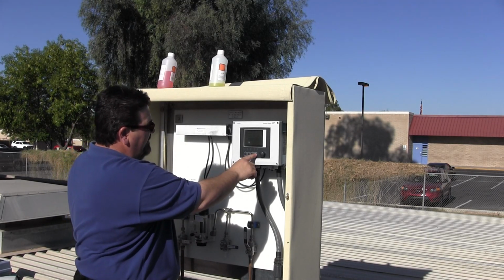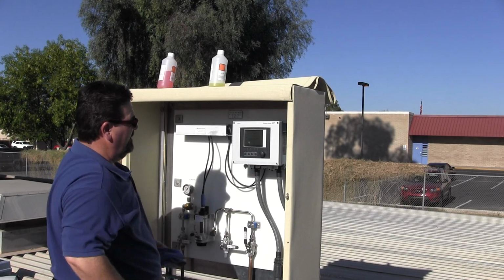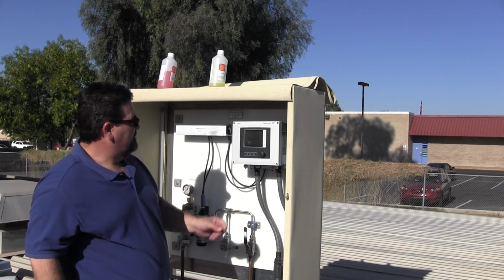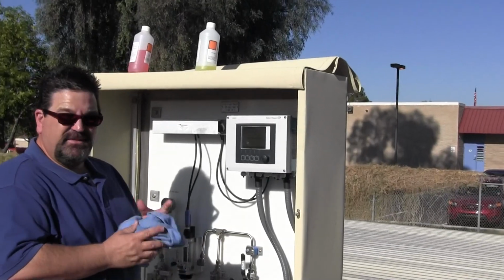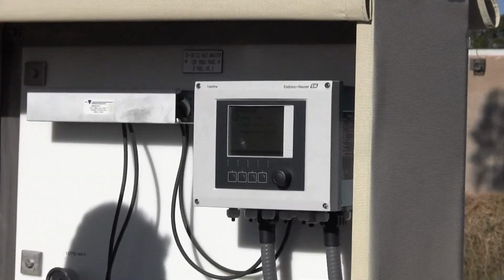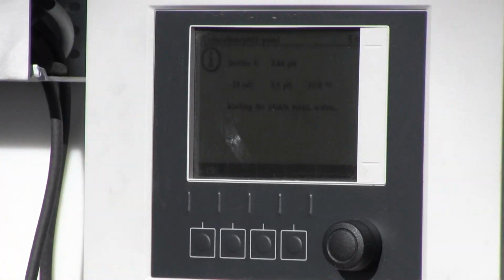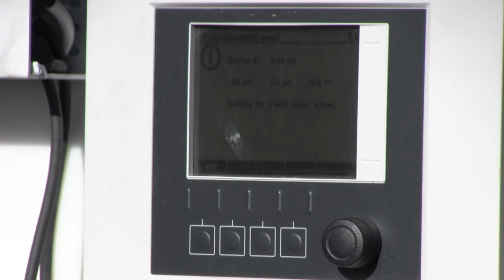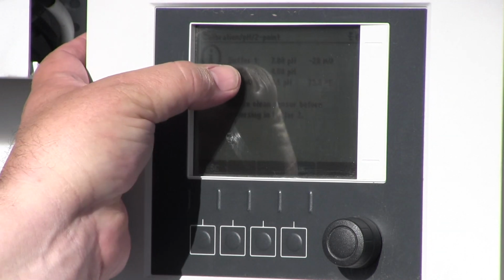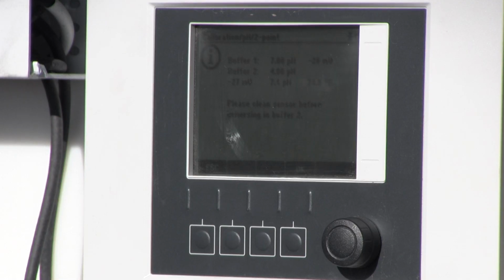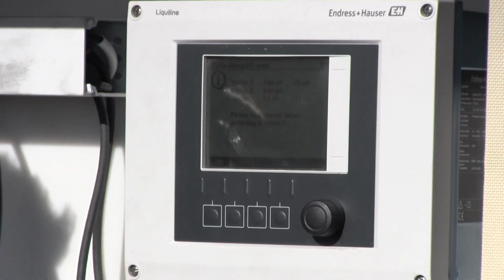We hit the OK button. It says waiting for stabilized measured value. The transmitter wants to make sure that the output from the pH electrode is not moving during the calibration process. It immediately has finished calibrating on the 7 buffer, and it now asks for buffer number 2, which is a 4 pH buffer.